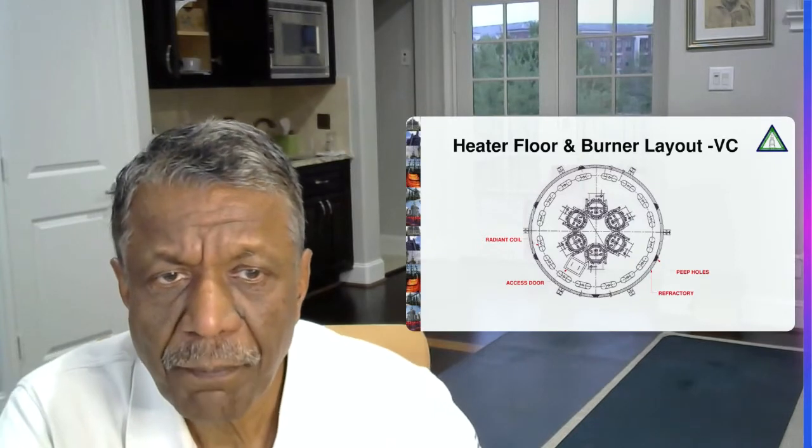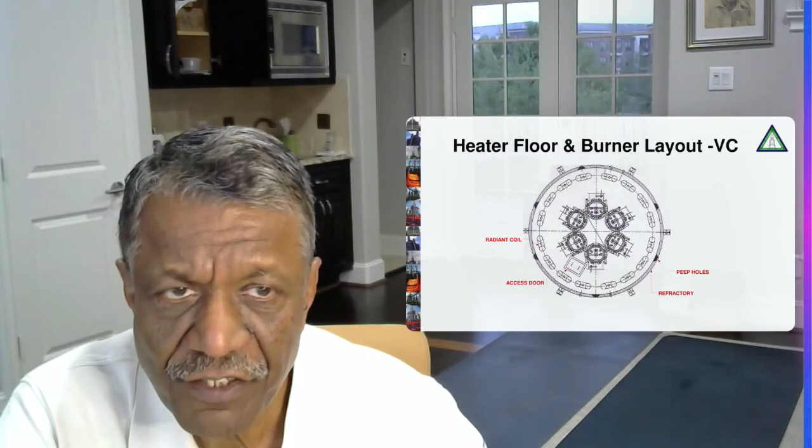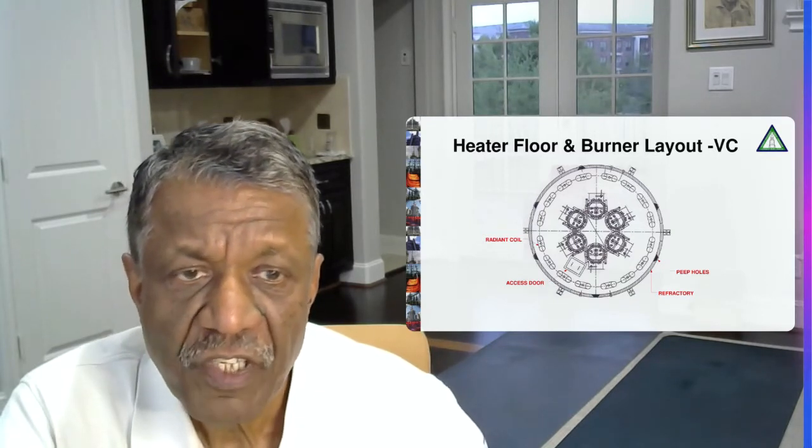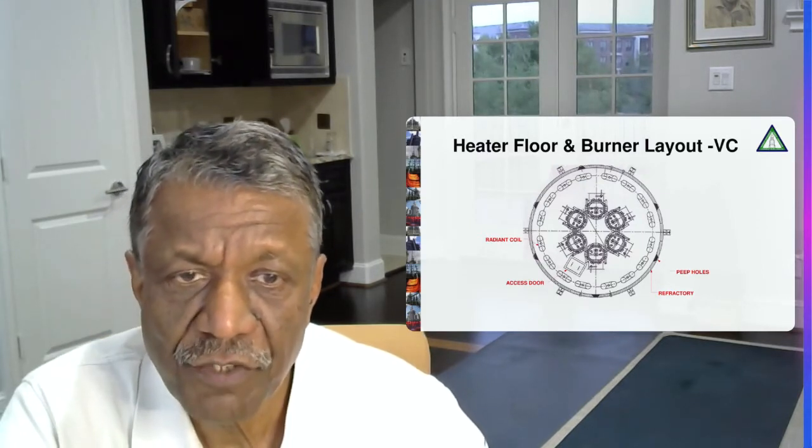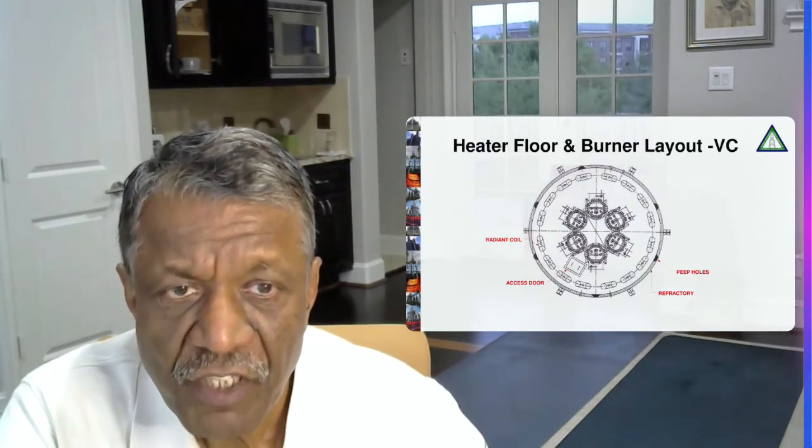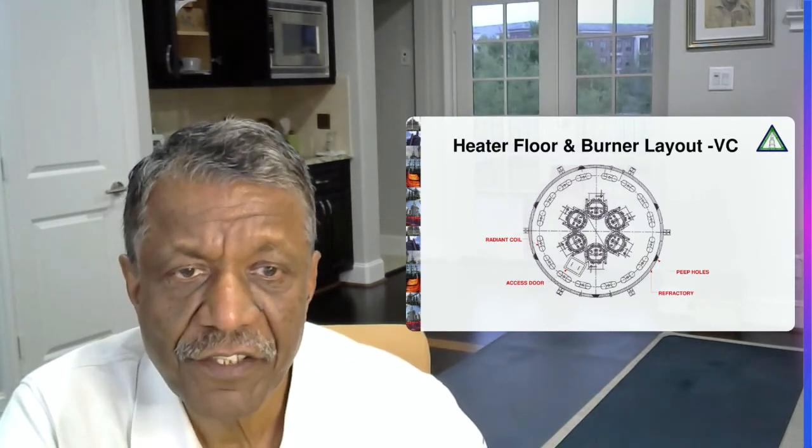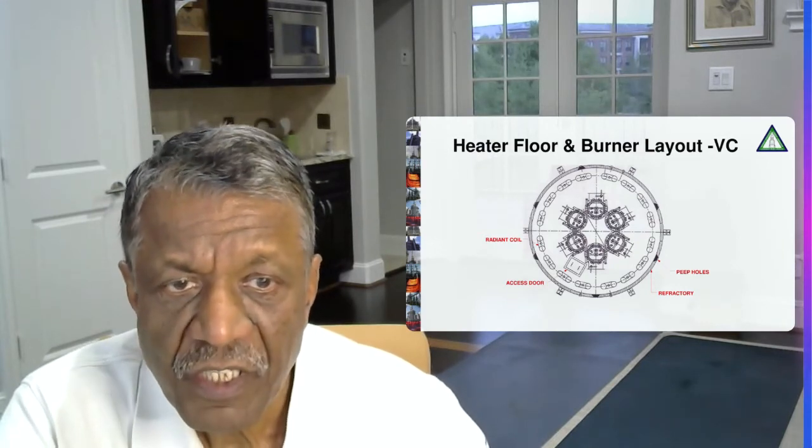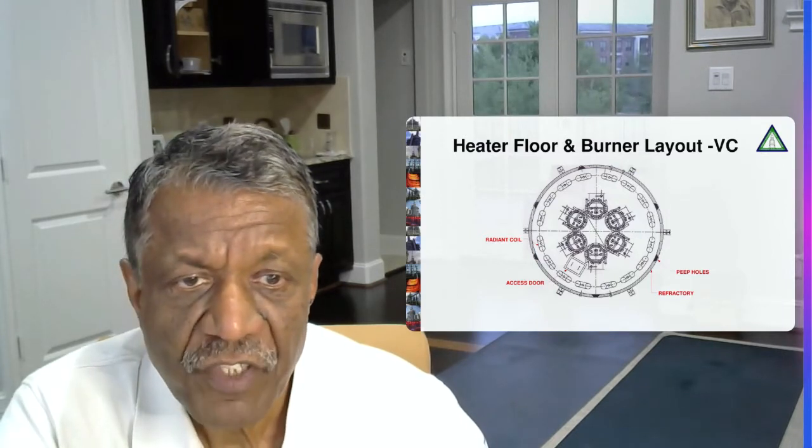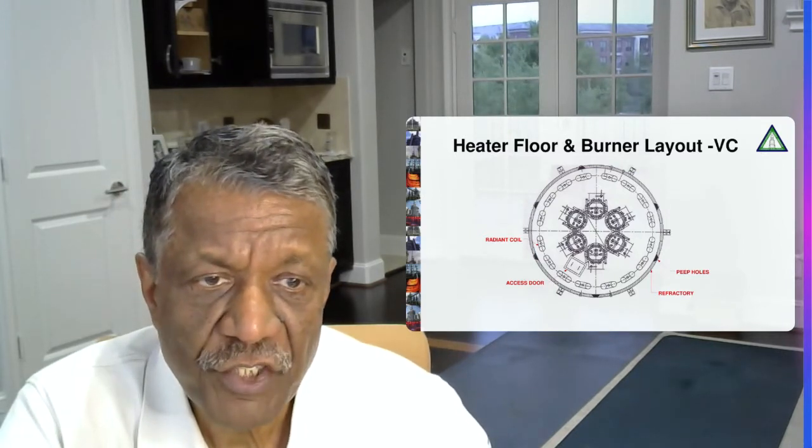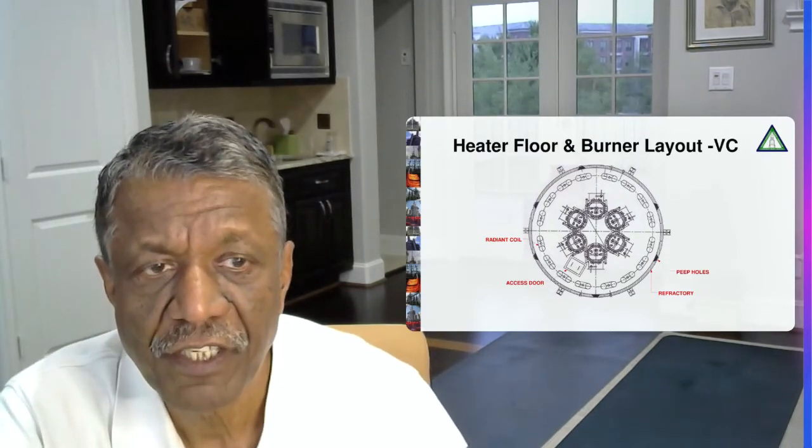I'm showing you a plan view of a vertical cylindrical radiant section. This is basically a heater floor view. You can see six burners installed in a circle. That circle is known as burner circle diameter. You can also see the radiant tubes which are installed again in a circle, and that circle is known as tube circle diameter. And then we have the refractory lining and steel casing on the outside. You can see an access door in this picture, you can see refractory lining and peep holes in this picture for a vertical cylindrical heater.